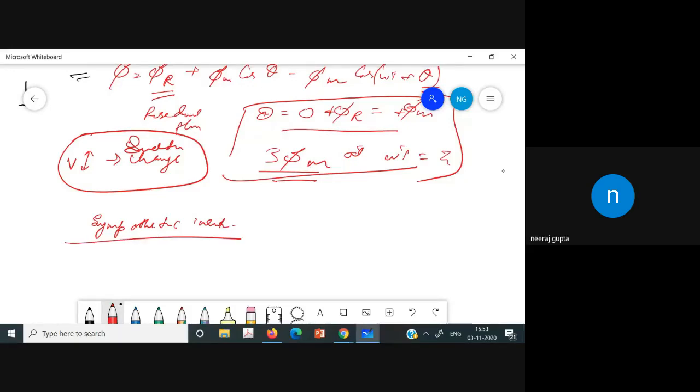Now, in the case of the protection system, if such a large current flows during the starting of the transformer on one side of the transformer, it looks like an internal fault to a differential scheme, and as a result, it ends up as a spill current.